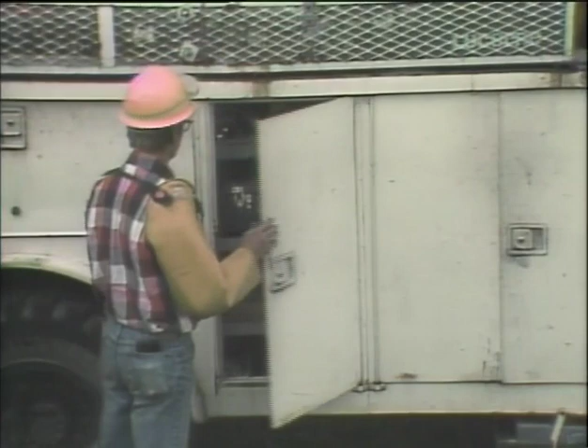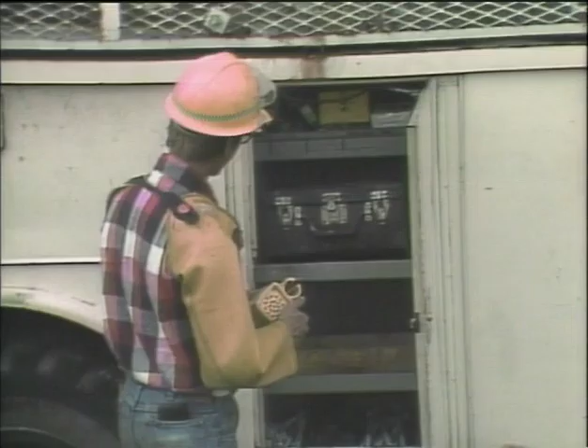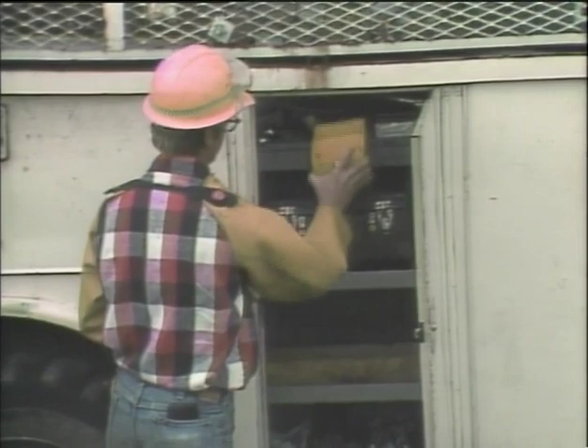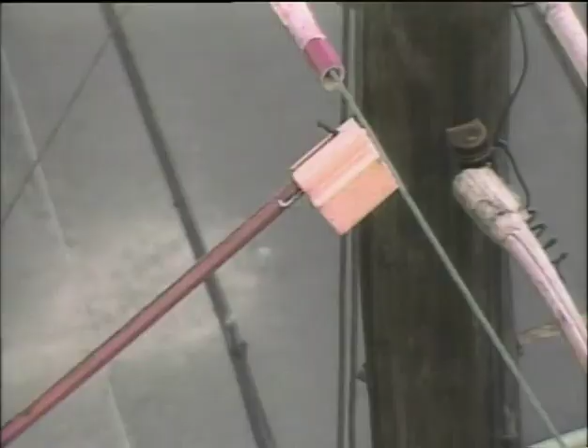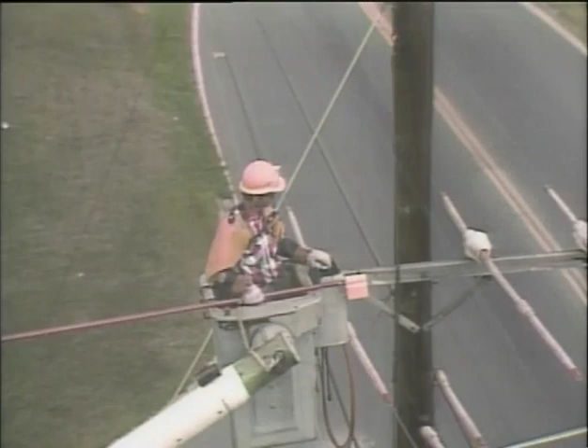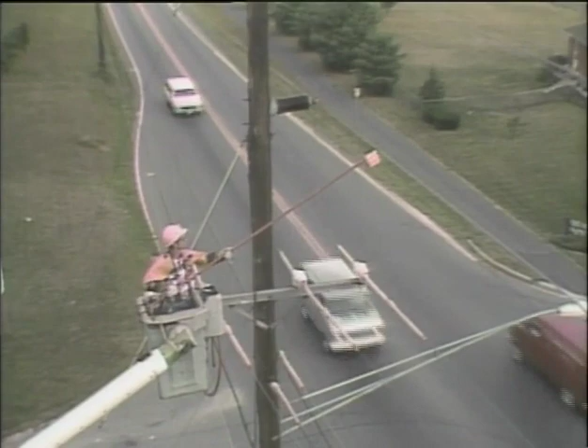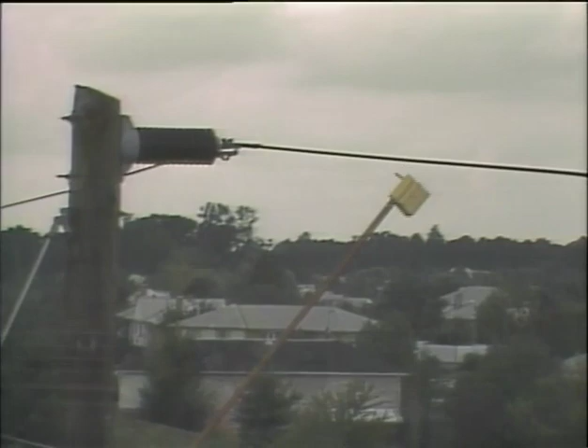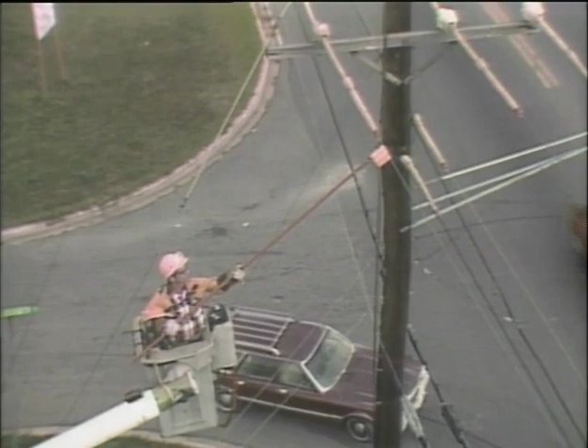On this job, the tester used is a noisy tester. The circuit to be tested is within the operating range of the noisy tester. The tester is checked by pressing the test button. The battery is okay. Now the tester is checked against a live power source. The tester works. The noisy tester is raised up to the lines to determine whether or not the circuit is dead. The tester makes no noise on this line, or this one, or this one. When the tester is rechecked, you can then assume your results are accurate and the circuit is dead.